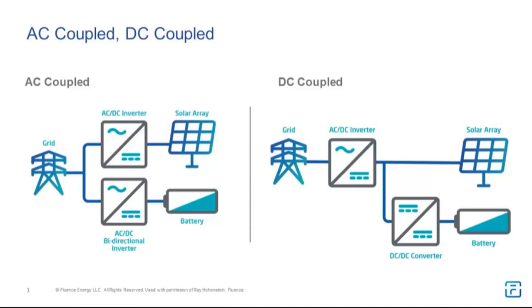That's why I've been a huge proponent of the DC coupled design on the right. The idea here is you actually put the batteries and the PV behind the same inverters. Conceptually, it's a single bidirectional inverter. There is a DC to DC converter, just because typically batteries and PV panels like to operate at different voltages, but from a market point of view, that disappears as well. These DC coupled resources sit behind a single 100 megawatt inverter, and that becomes a single resource, which no longer really looks like PV or battery. It's now something new.